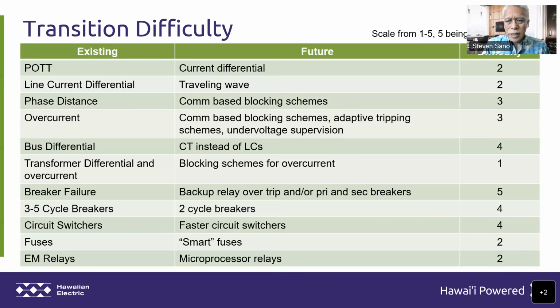Phase distance to communication-based blocking schemes, because we probably don't have communication for some of these locations, it's a 3. A little bit more difficult. Supervised overcurrent with communication, adaptive schemes, voltage, that sort of thing. And then sort of a 3 as well. Bus differential protection changes, getting rid of those linear couplers, which we have been desperately trying to do. That's up at a 4, just because of our station designs and the criticality of those buses. Sort of an existing situation that we'll have going into the future.